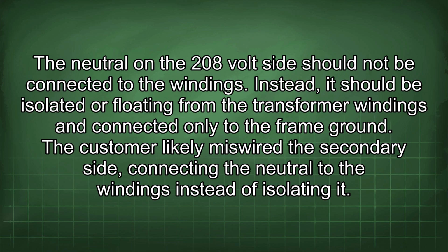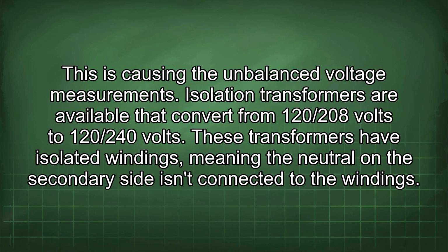The customer likely miswired the secondary side, connecting the neutral to the windings instead of isolating it. This is causing the unbalanced voltage measurements. Isolation transformers are available that convert from 120/208 volts to 120/240 volts. These transformers have isolated windings, meaning the neutral on the secondary side isn't connected to the windings.